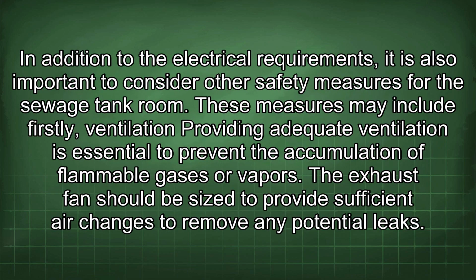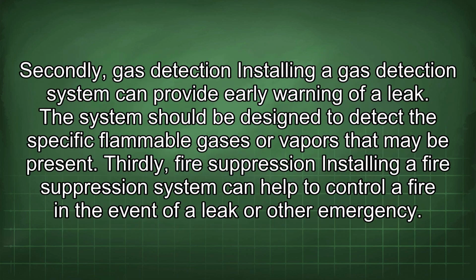In addition to the electrical requirements, it is also important to consider other safety measures for the sewage tank room. These measures may include, firstly, ventilation. Providing adequate ventilation is essential to prevent the accumulation of flammable gases or vapors. The exhaust fan should be sized to provide sufficient air changes to remove any potential leaks. Secondly, gas detection. Installing a gas detection system can provide early warning of a leak. The system should be designed to detect the specific flammable gases or vapors that may be present.